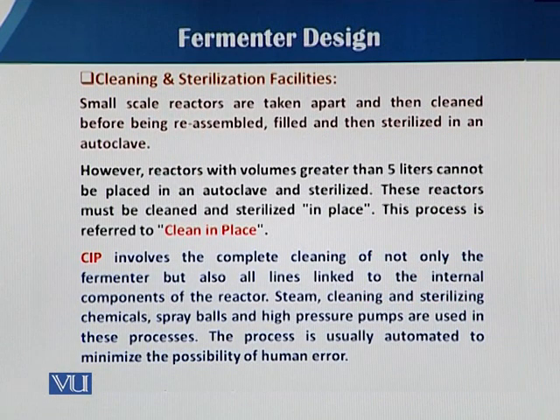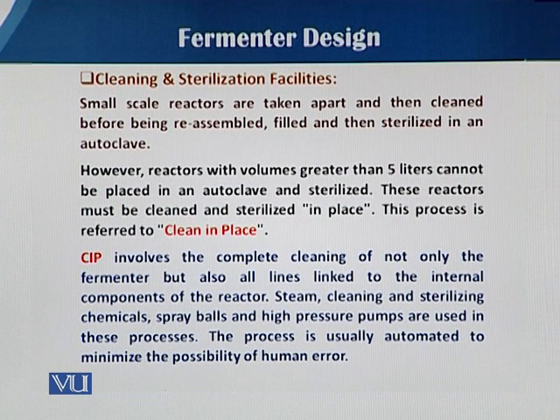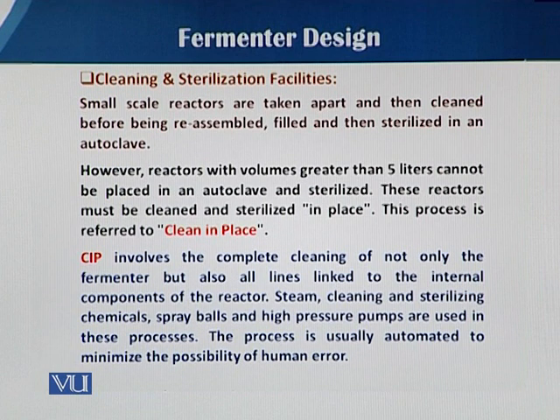If we have a fermenter that has to be used for a number of operations and for continuous use, from one batch to another batch we need cleaning. Small-scale reactors are taken apart and cleaned before being reassembled — their cleaning is carried out ex-situ. We disassemble the whole fermenter and utilize the autoclave. For large fermenters, we have to clean them in situ, which is known as Clean in Place, or CIP.